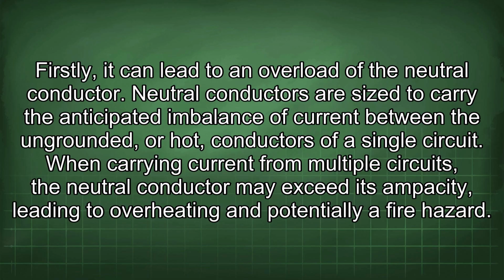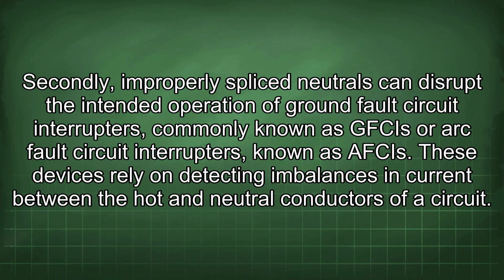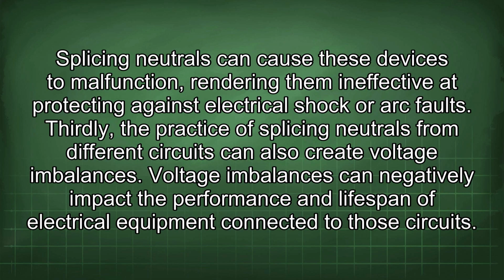Neutral conductors are sized to carry the anticipated imbalance of current between the ungrounded, or hot, conductors of a single circuit. When carrying current from multiple circuits, the neutral conductor may exceed its capacity, leading to overheating and potentially a fire hazard. Secondly, improperly spliced neutrals can disrupt the intended operation of ground fault circuit interrupters, commonly known as GFCIs, or arc fault circuit interrupters, known as AFCIs.